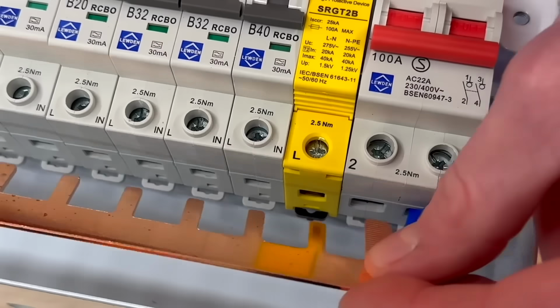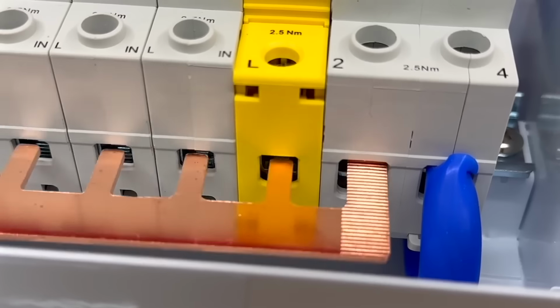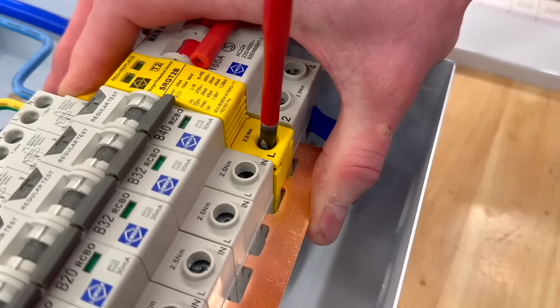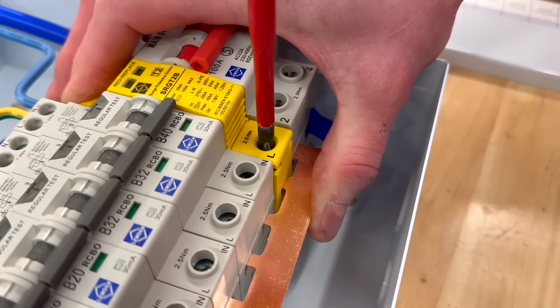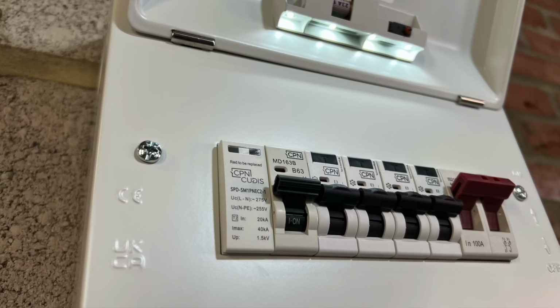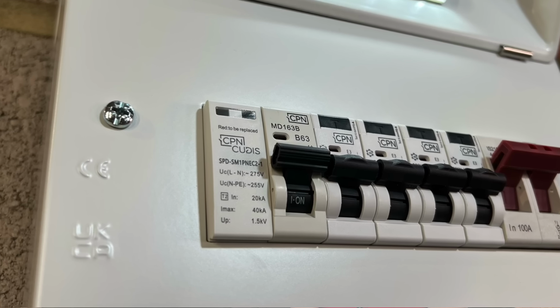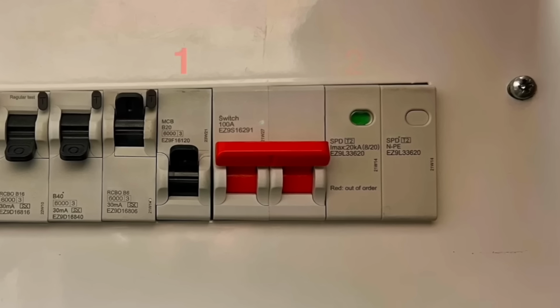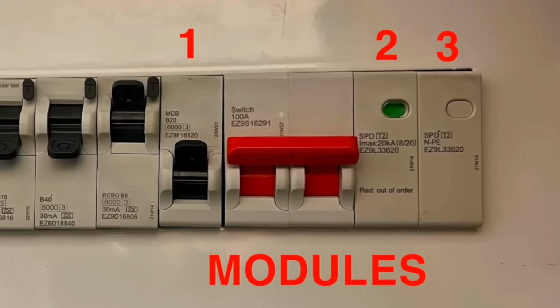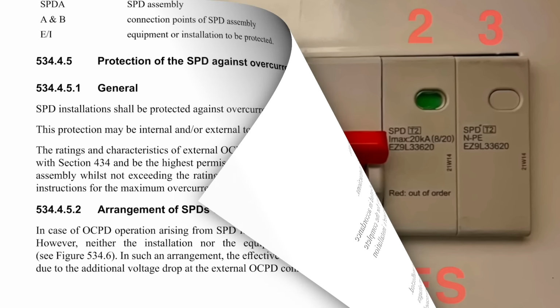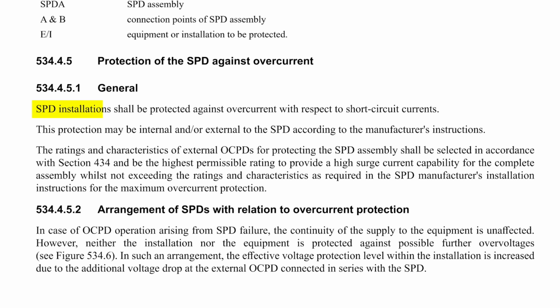Other brands such as Linian have developed SPDs with built-in fault protection which they say don't need an additional MCB. Meanwhile, some other manufacturers say their surge protection devices do require one. But the problem for installers is that these can take up to 2 or even 3 valuable module spaces in a consumer unit. Regulation 534.4.5.1 says that SPD installations shall be protected against overcurrent. It goes on to say that this protection can be internal to the SPD according to the manufacturer's instructions.